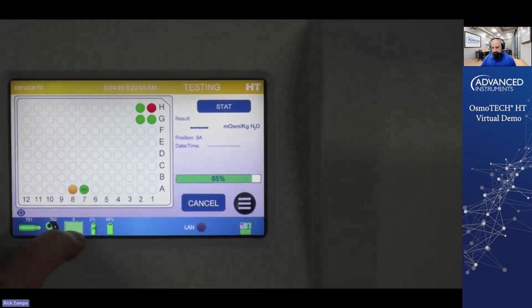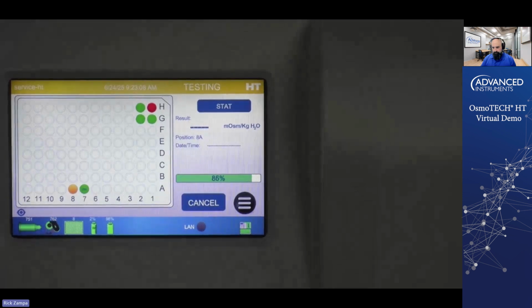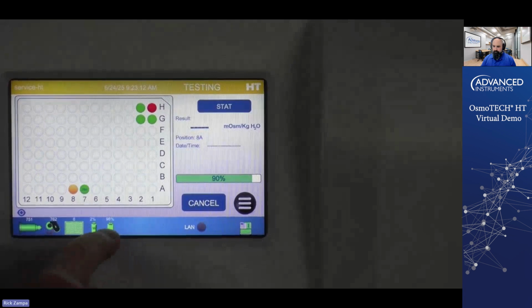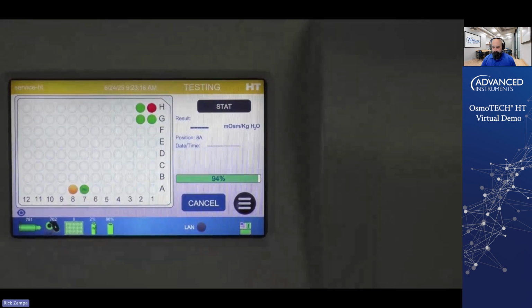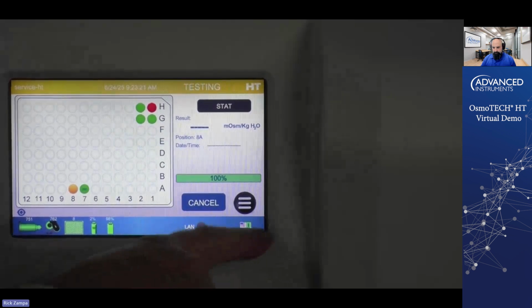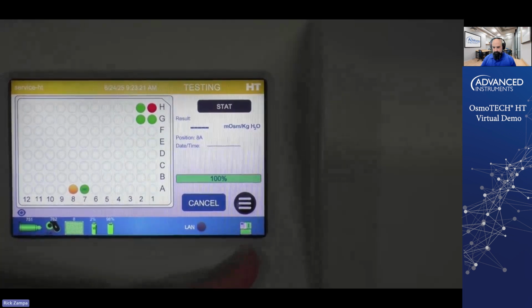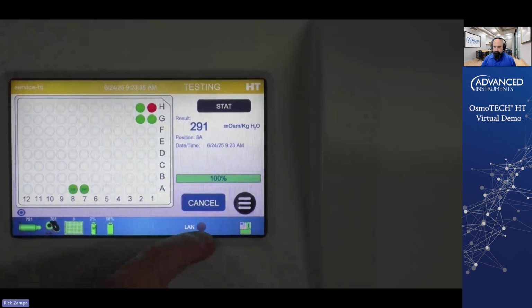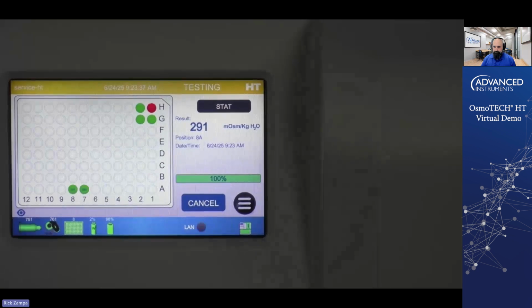The number of plates left, as I said, the system comes with 11 plates. We've used 8 of those plates up already. And then our cleaning fluid in our waste bottle shows you how much is left in the cleaning fluid, so you know when to change that. You also have over here an indicator that shows you if any of your doors are open. I have one door open, but I've overridden the system. I'm not going to tell you how to do that, but it's just so we can do that for demonstration purposes. We have our LAN button here, which shows whether we're connected to the LAN network.